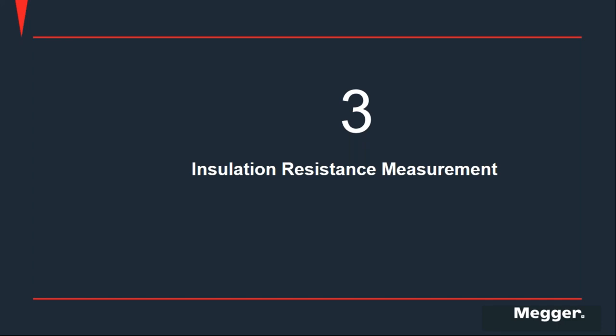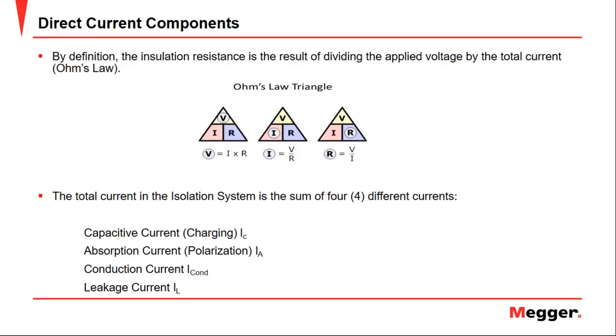Okay, now let's take a look at the most famous and performant static test of all, the insulation resistance test. When we talk about the insulation resistance measurement, all the equipment that does it relies on one important law to deliver the resistance value, and that is Ohm's law. This is defined as the relationship that exists between the injected voltage and the current measured. However, it is necessary to understand the behavior of the current when the motor is supplied with a DC voltage. And precisely that is what we're going to see in the following slides.